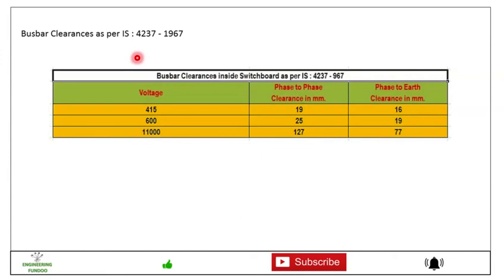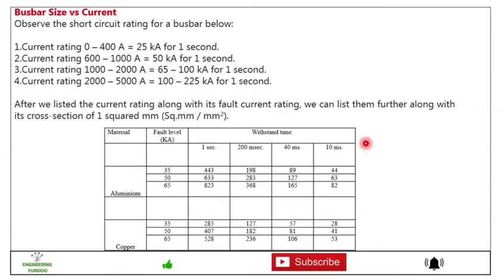Friends, then there will be a busbar clearance as per IS 4237-1967. Busbar clearance inside the switchboard as per IS 4237-1967. For voltage 415, phase to phase clearance in mm required is 19 mm, phase to earth clearance required is 16 mm. For 600 voltage, phase to phase clearance required is 25 mm, phase to earth clearance required is 19 mm. Similarly for 11000 voltage it will be 127 and 77.